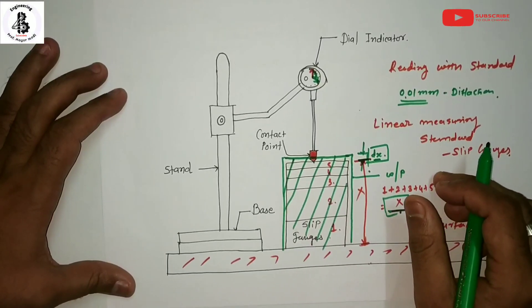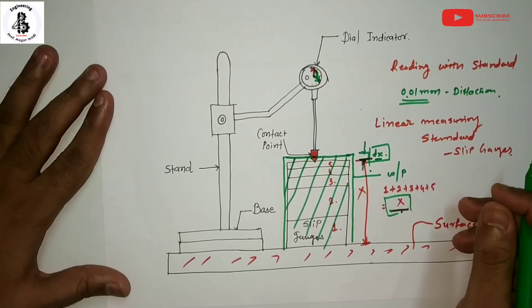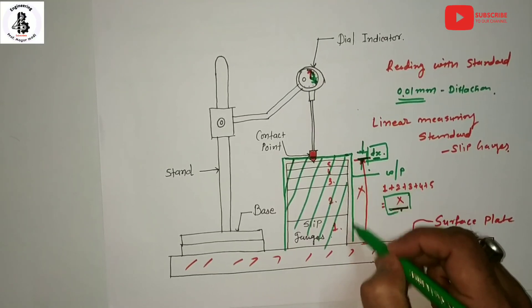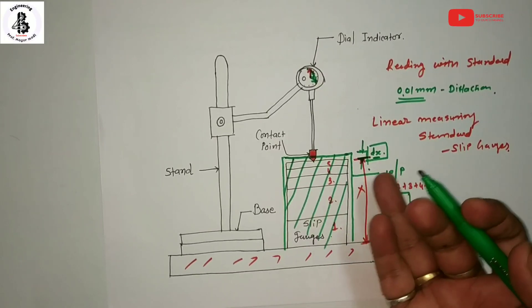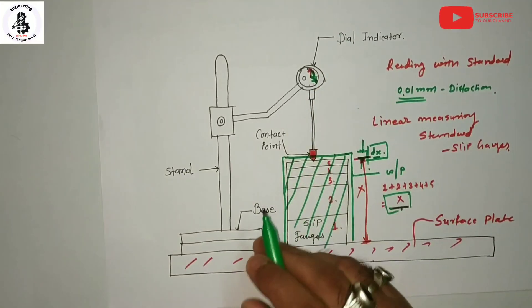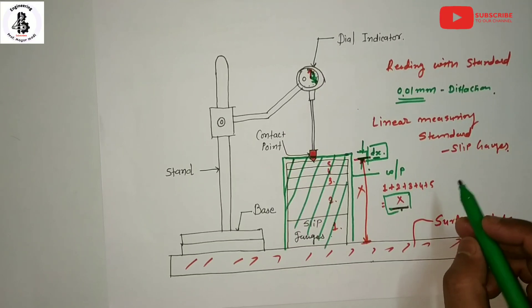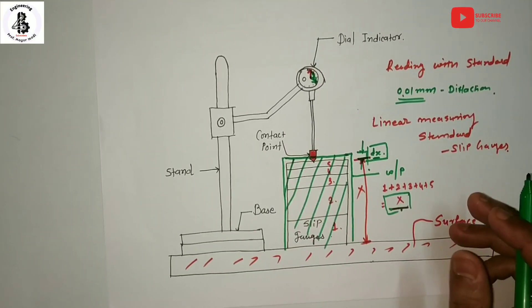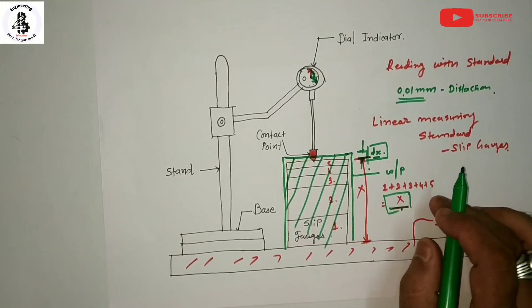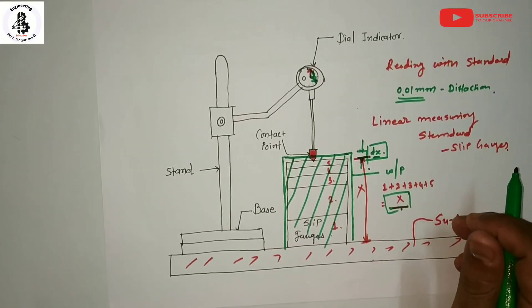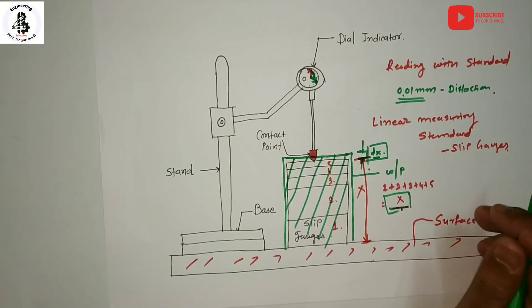Most alignment testings can be performed with the help of dial indicators. Advantages include: first, comparing the height of two components to determine which is higher; second, determining errors in geometrical forms such as ovality, roundness check, and tapering; and third, taking accurate measurements of deformations in tensile and compression testing of materials. These are all the applications of the dial indicator, including use in alignment testing of machines. If you like this, please subscribe and share. Modi Mechanical Engineering Tutorials. Thank you very much.